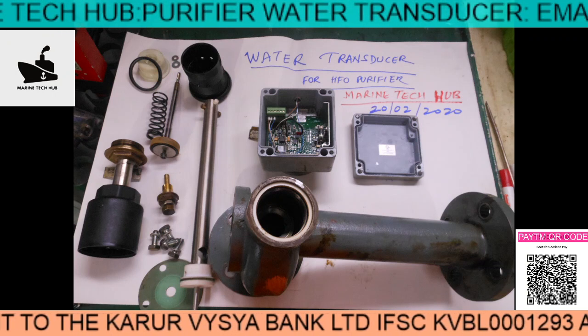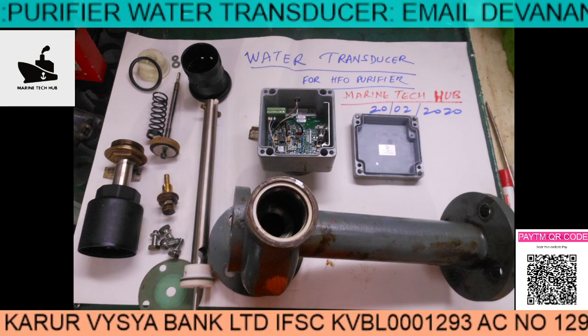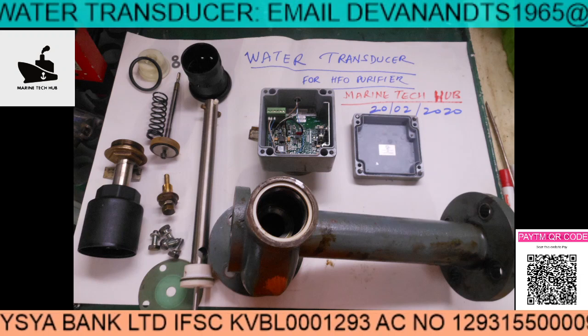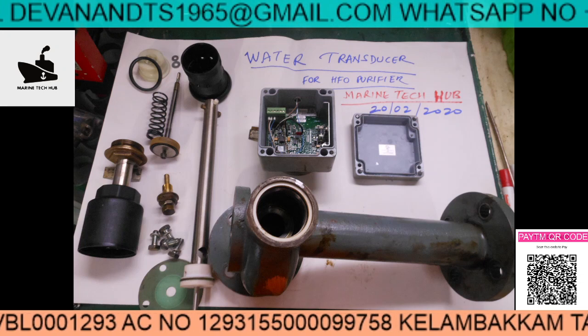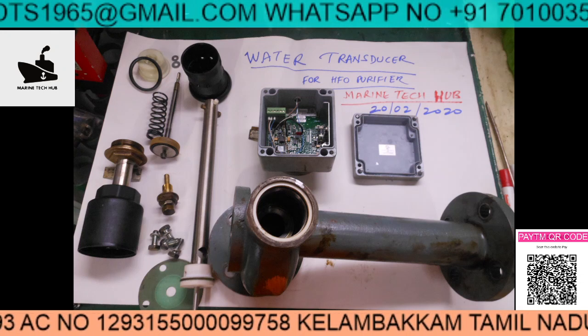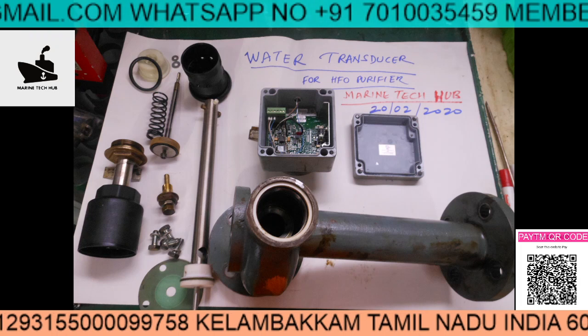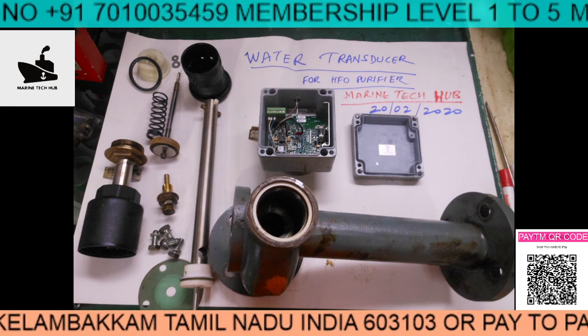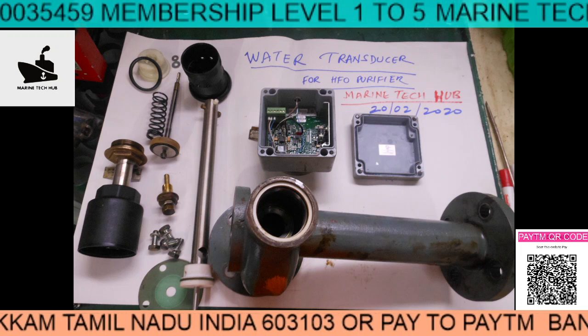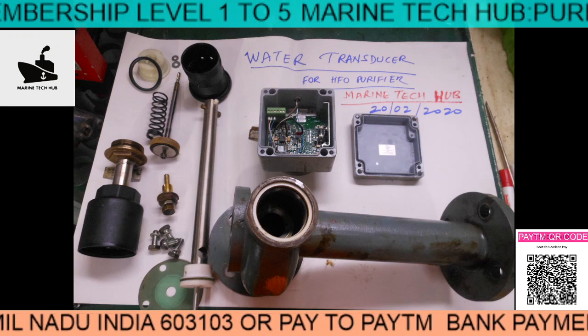It is very difficult to take this out because the Teflon piece is fabricated and concealed inside. I fabricated it and the problem in this case was a blown fuse and a lot of dirt on the capacitance.